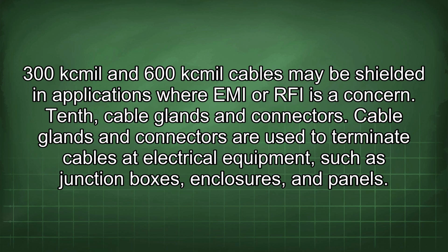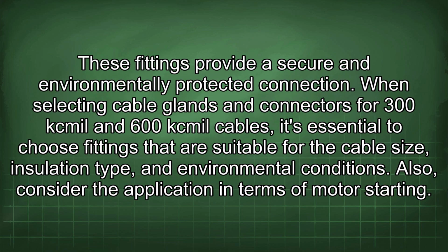10th, cable glands and connectors. Cable glands and connectors are used to terminate cables at electrical equipment, such as junction boxes, enclosures, and panels. These fittings provide a secure and environmentally protected connection. When selecting cable glands and connectors for 300kcmil and 600kcmil cables, it's essential to choose fittings that are suitable for the cable size, insulation type, and environmental conditions.